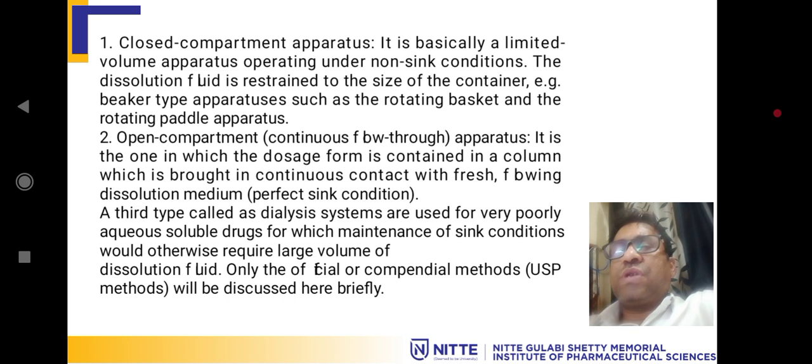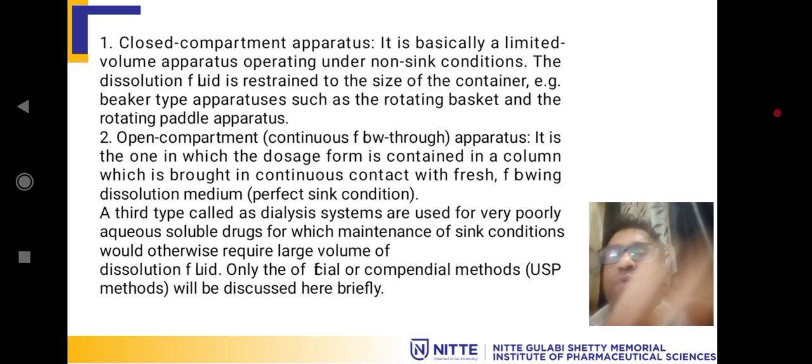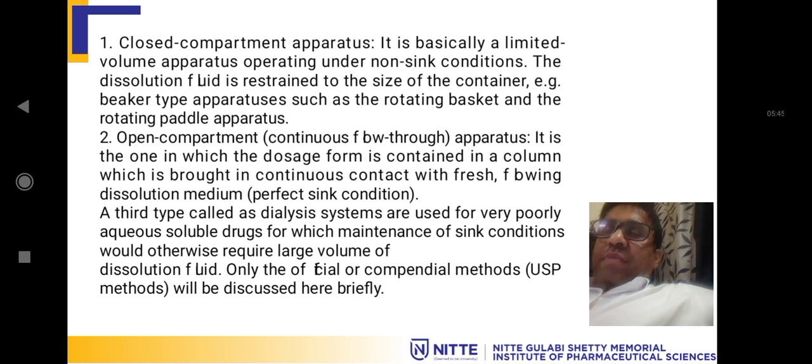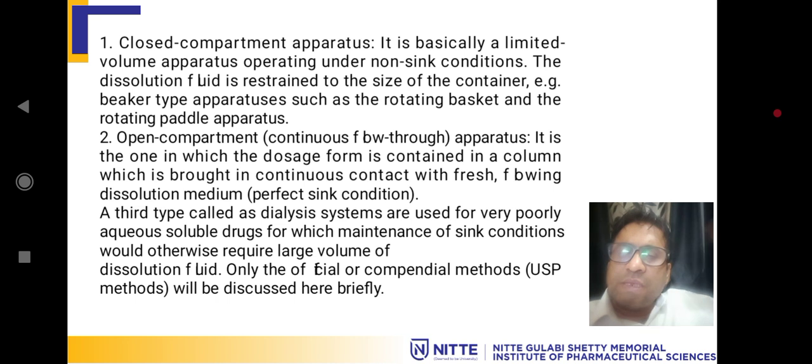The first one, closed compartment, is basically a limited volume apparatus operating under non-sink condition. The dissolution fluid is restrained in size, so restrained by the size of the container. Beaker type apparatus such as the rotating basket and rotating paddle apparatus are examples.